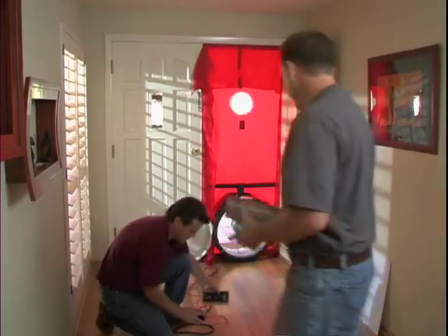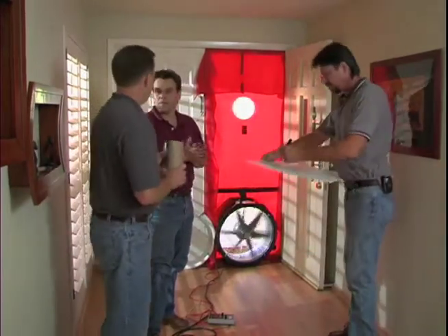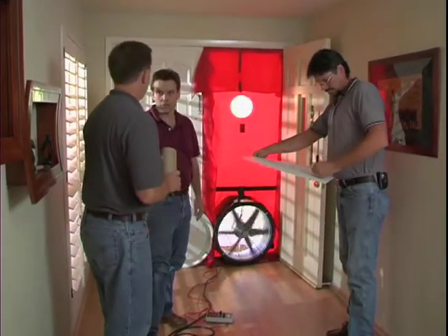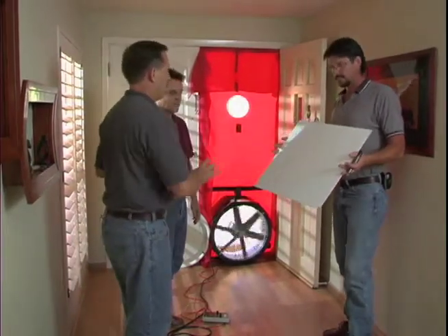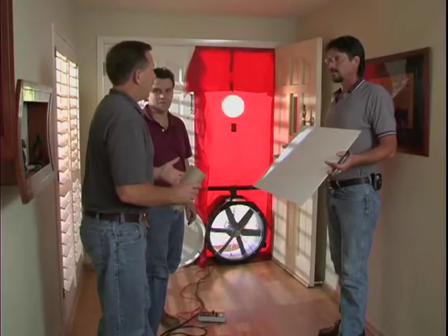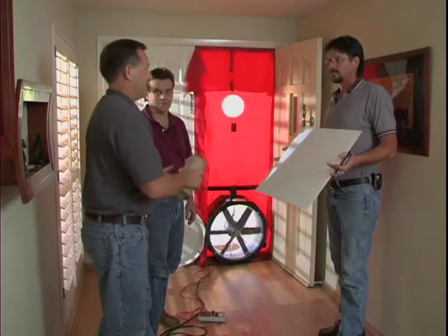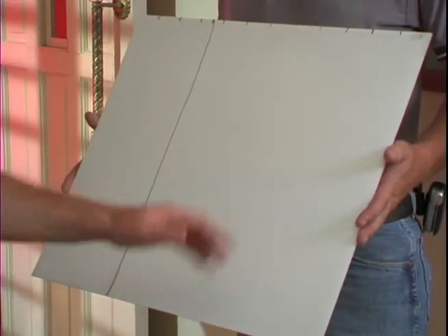All right, all sealed up. What do we got? About 3,400 CFM50. That's about 340 square inches. Oh, that's a lot. That's about that much. That much overall, which means this is the duct leakage we're looking at. Correct. Well, I know you guys have some equipment to help us identify those leaks, but the rest of this, how do we identify and take care of that?